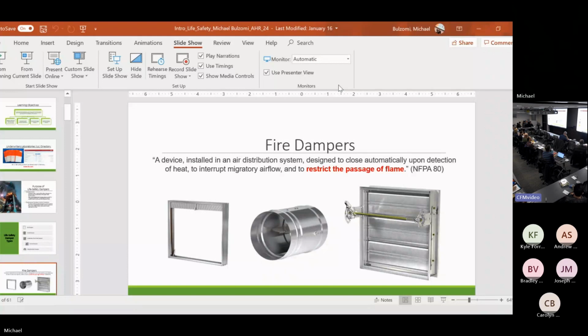So in the event of a fire, that damper closes. The continuity of that barrier is now maintained, right? That's all we care about, not smoke. Fire dampers are not leakage rated, not heat. There is no thermal properties to this blade. It's metal. Heat will pass right through it. Nothing else, just the passage of flame.